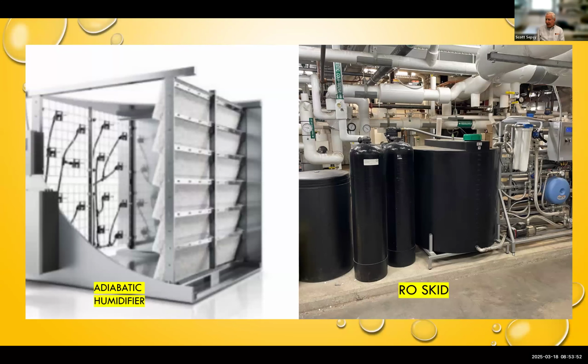Control sequences on air handlers need to change because the air must be heated by the preheat coil higher than normal, to around perhaps 80. This varies with load and entering conditions, compared with our normal 50, 55-degree air. And then with the adiabatic humidification, the preheated air is recooled as it passes over the grid of the RO spray nozzles shown on the left, which absorb the water into the airstream and cool the airstream. So you end up with the same process leaving the air handler.